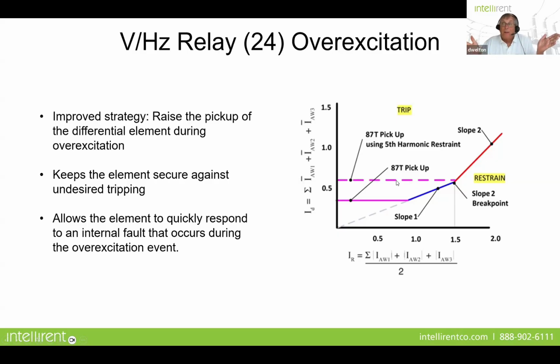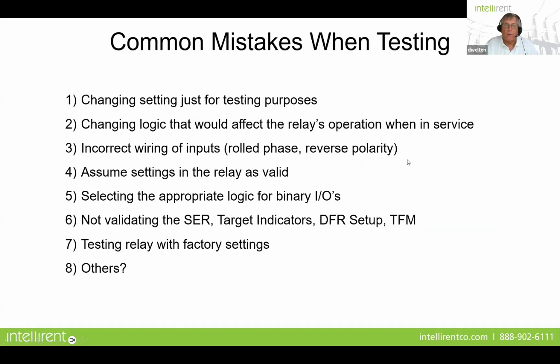Let's say you have a fifth harmonic blocking going on because of a volts per hertz condition, and at the same time you have a fault internal to the transformer. Okay, so it's a little convoluted, and I don't know if it's ever really happened, but if it did happen, we'll still have some protection in the higher restraint area up here.